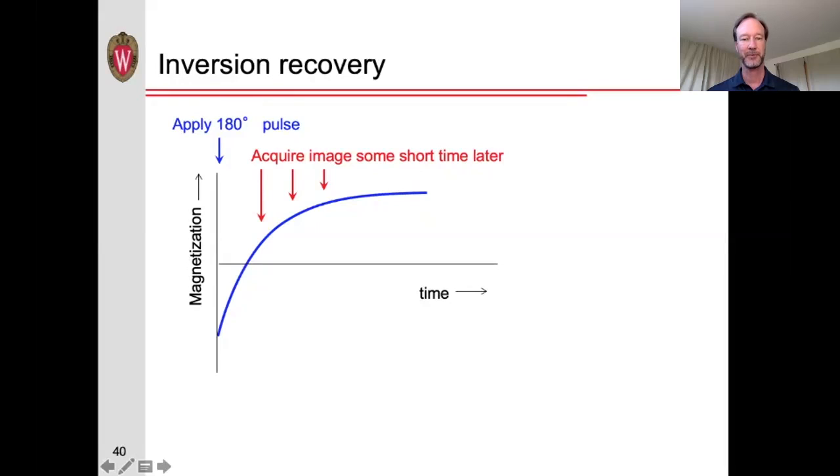So, for example, we can create images where we have removed the signal from the CSF. That is, all the signal from the CSF will appear black or dark in the image. It's a technique called CSF nulling. So we apply a 180-degree pulse. We wait for a certain period of time until that T1 crosses the zero. And then we crush the remaining transverse magnetization and then acquire our image from that.